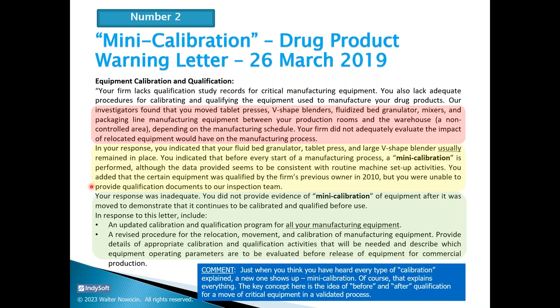Oops. Remember I told you to review your legacy qualification data to see if it's even available to be reviewed? You may want to do that before an inspection comes up. Your response was inadequate. You did not provide evidence of mini calibration after it was moved to demonstrate it continues to be calibrated and qualified before use. In response to this letter, include an updated calibration qualification program for all your manufacturing equipment.